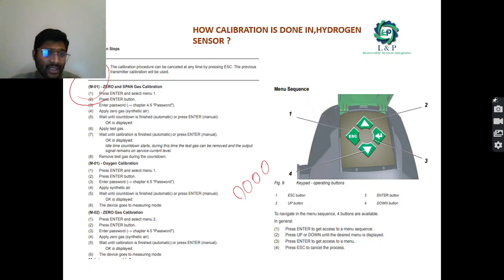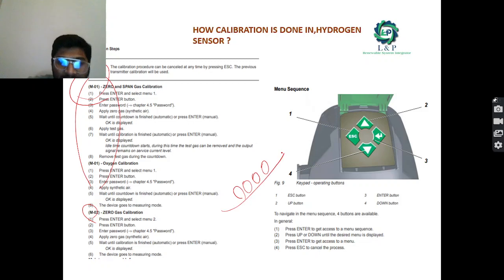Using the same way, we can do the oxygen calibrations and zero calibrations also. If you want to do the span gas calibration, the oxygen calibration, you go inside the M01 menu, and if you want to do the zero gas calibration, you go inside the M02 menu. Same process: press enter, select menu 2, and enter the password. Apply the zero gas. Wait until the calibration is finished, or press the enter button. Once it is done, the device will go to the measuring mode.